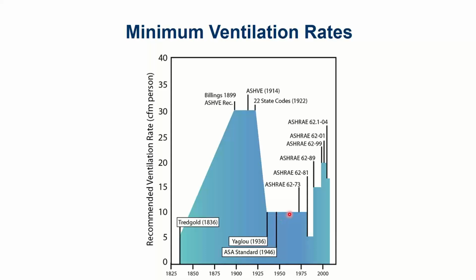10 CFM per person was pretty common. We went down to 5 CFM per person in the 70s as a reaction to the energy embargo. And that was a mess because it caused sick buildings. So we had to undo that. So at ASHRAE, we overcompensated the other way and tripled it up to 15 CFM per person, then eventually 20 CFM per person. And right now we're at approximately 17.